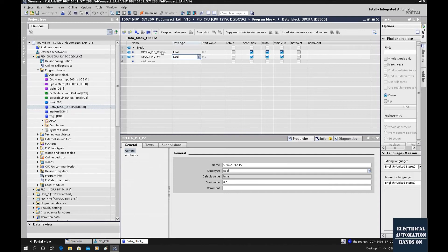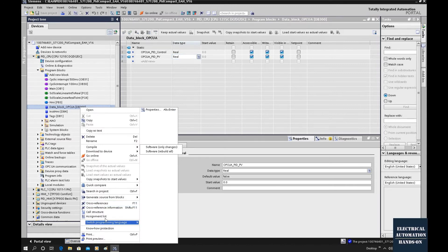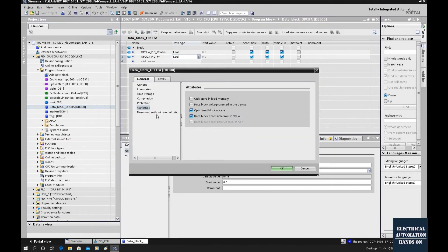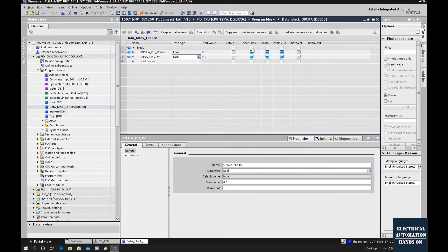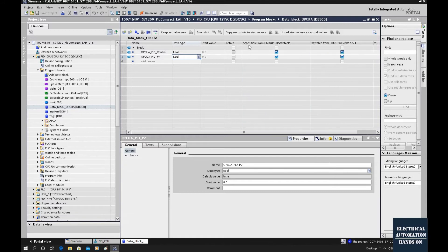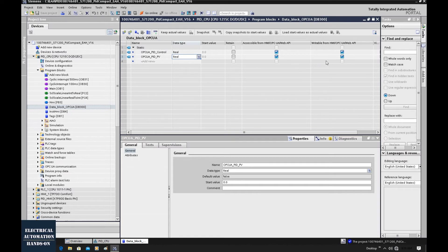Their data type is real (float). To allow these two tags to be communicated through OPC UA, we need to check one property of this DB. Right-click, go to Properties, and verify that the data block is accessible from OPC UA — by default it should be checked. Then check the detail settings: make sure 'Accessible from HMI/OPC UA' is enabled for both tags. These are the read and write permission settings, and we will check all of them.